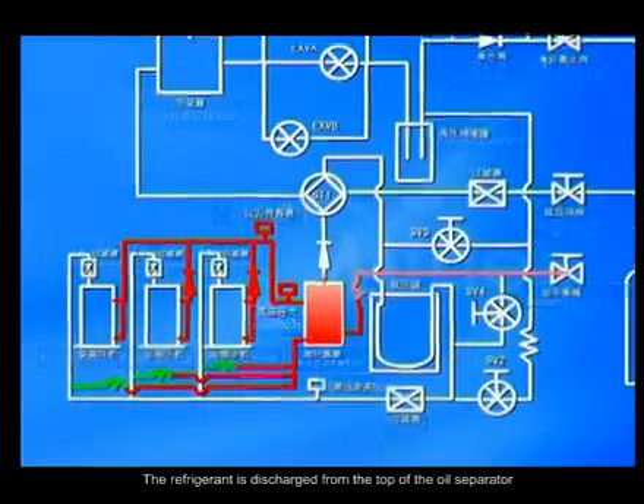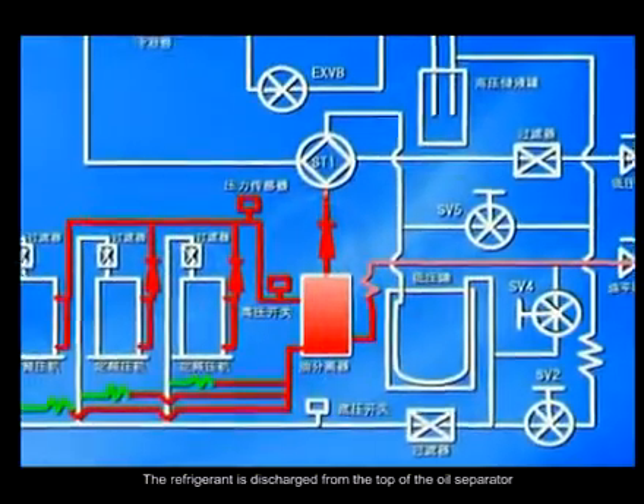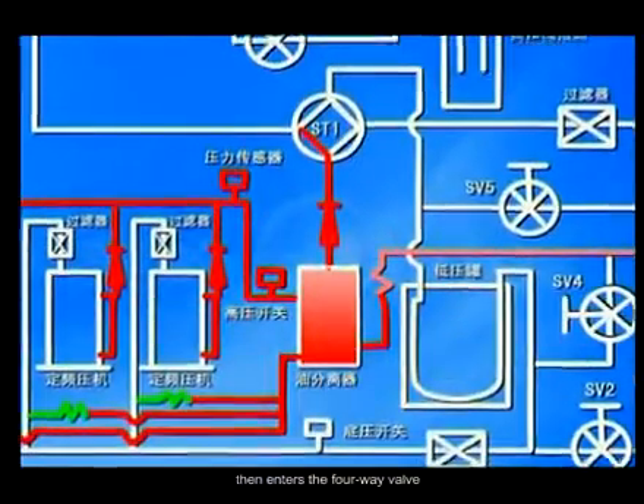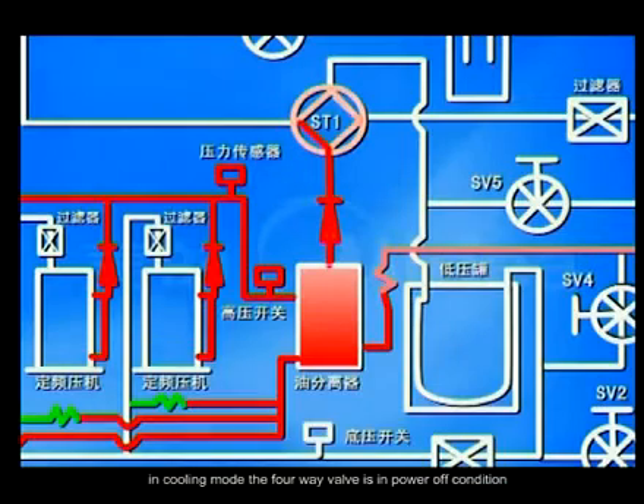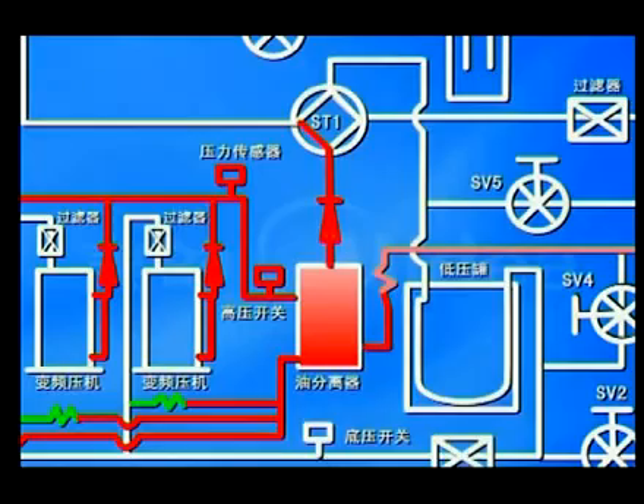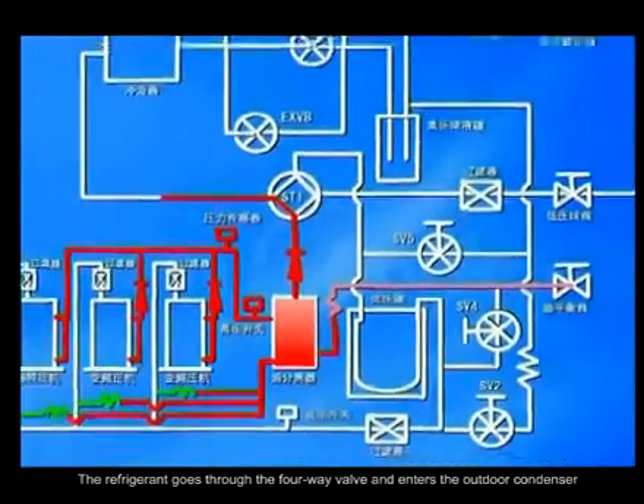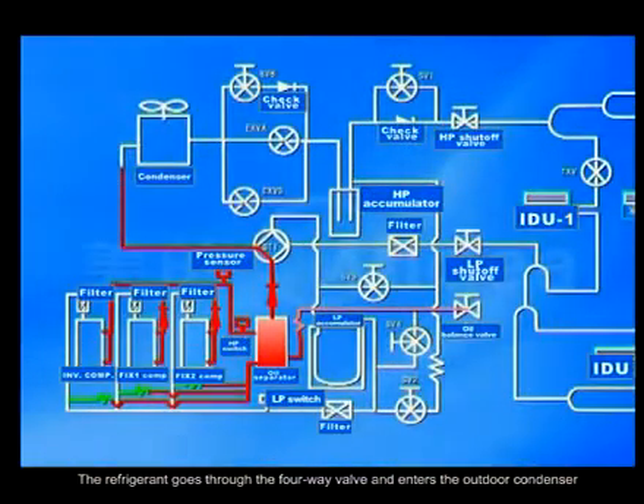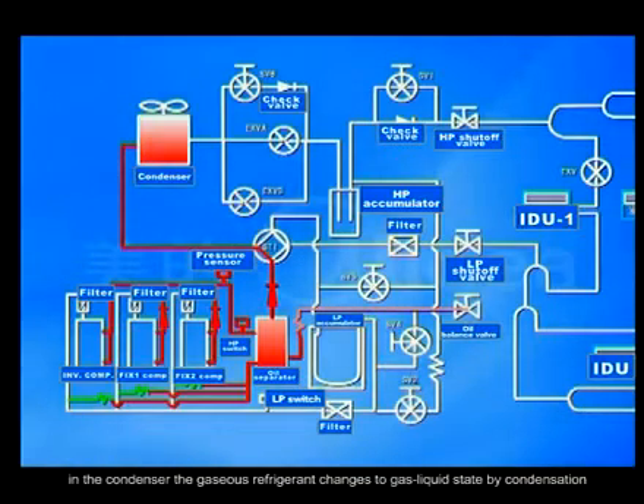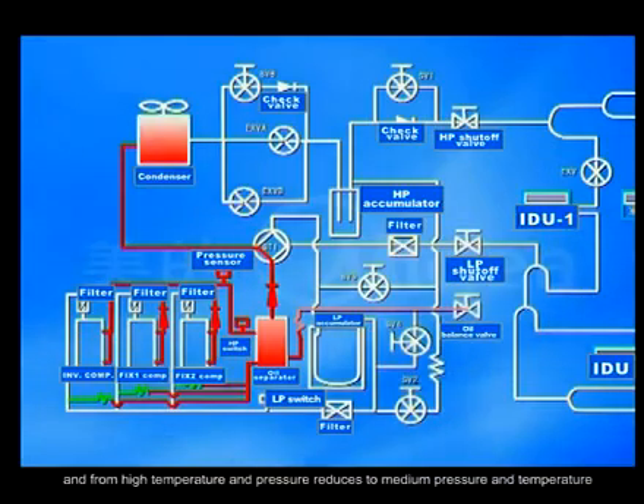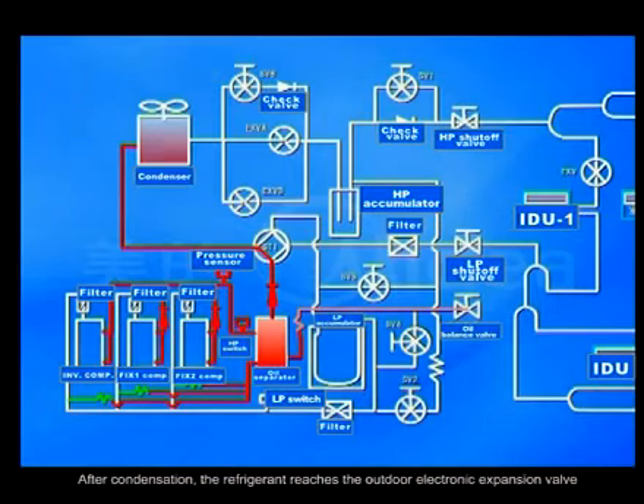The refrigerant is discharged from the top of the oil separator, then enters the 4-way valve. In cooling mode, the 4-way valve is in power off condition. The refrigerant goes through the 4-way valve and enters the outdoor condenser. In the condenser, the gaseous refrigerant changes to gas-liquid state by condensation, and from high temperature and pressure reduces to medium pressure and temperature. After condensation, the refrigerant reaches the outdoor electronic expansion valve.